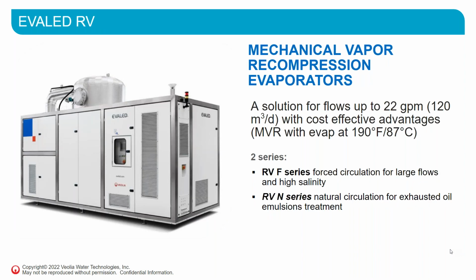Okay. And then our last system is the RV series, and this is a mechanical vapor recompression evaporator. This one is for higher flows, up to 22 gallons per minute. Where I would say the first two units are almost completely hands-free operation, with very limited maintenance and oversight required, the RV unit is certainly very energy efficient, but it requires a little bit more maintenance attention. But in the right application, this is certainly the right technology, in that it runs very energy efficient, about 3 times the efficiency of the other units.